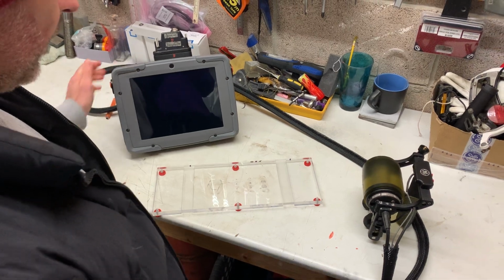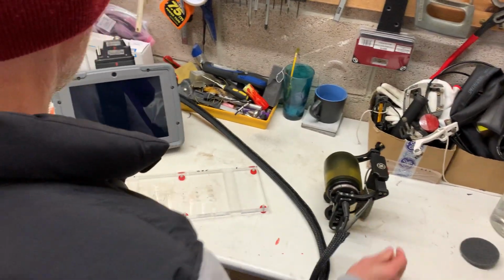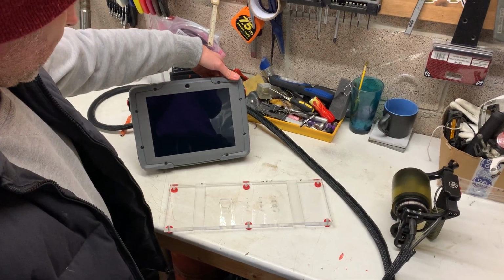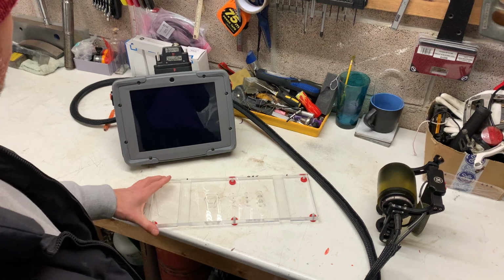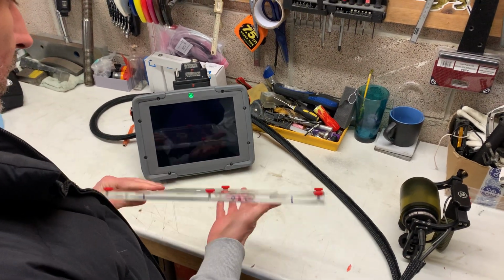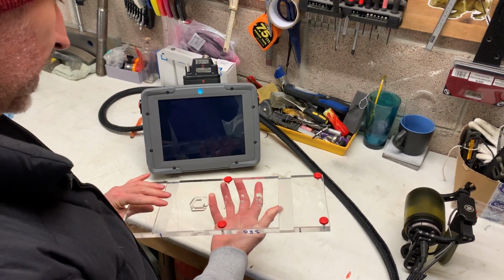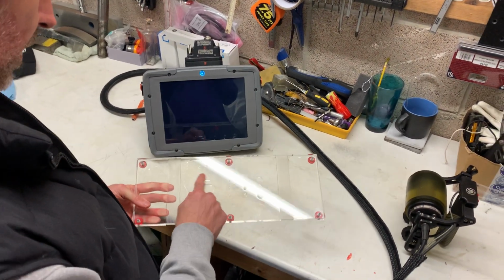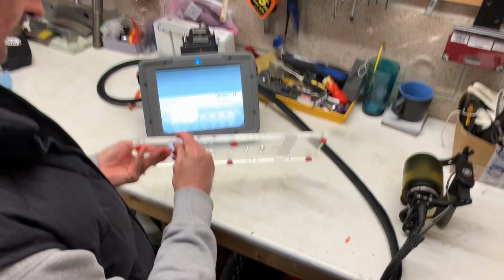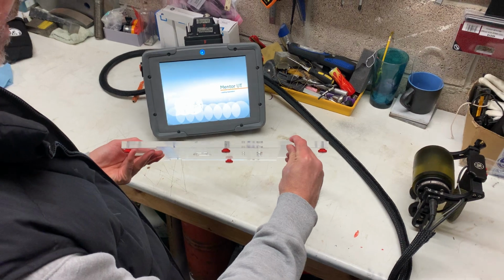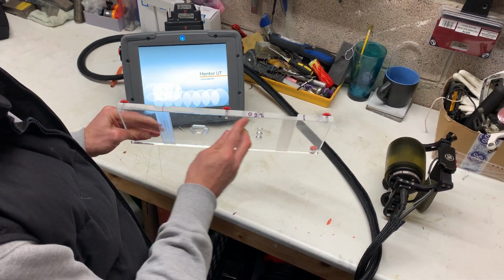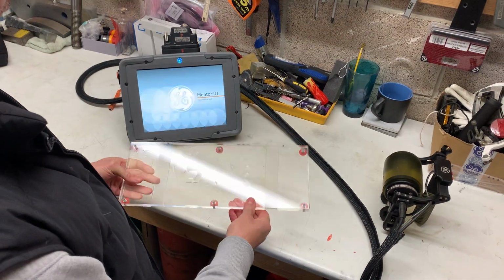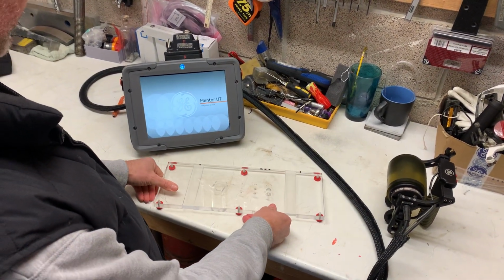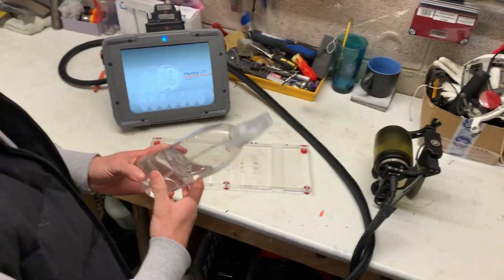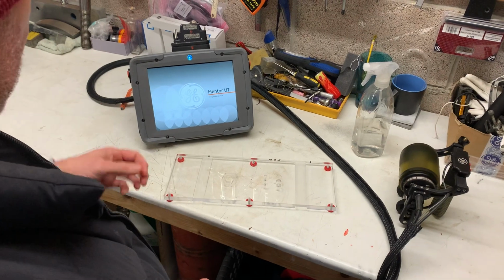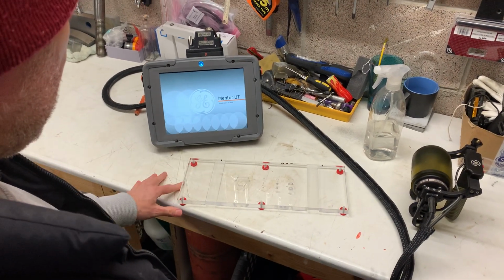Got our Mentor UT, and we've got our trusty 5 meg roller array. So we'll just reach around here and we'll switch the Mentor UT on. Just takes a couple of seconds for that to come on. So let's just have a look at this. It's pretty similar to the old GE one, except with this Waygate logo, and that's 10mm there, that's 6.5mm there, and then I've got 250 marked out between those two black lines to do the encoder calibration in a little bit. What else I need is a spray bottle with some water in. Just water in that, and then when the instrument boots up, we'll be ready to start.